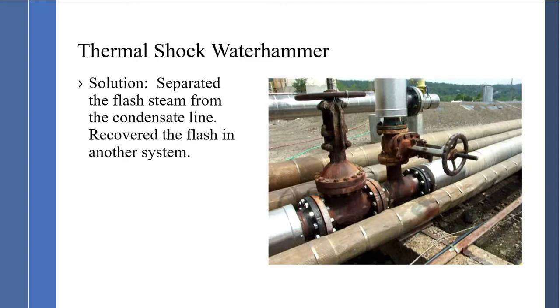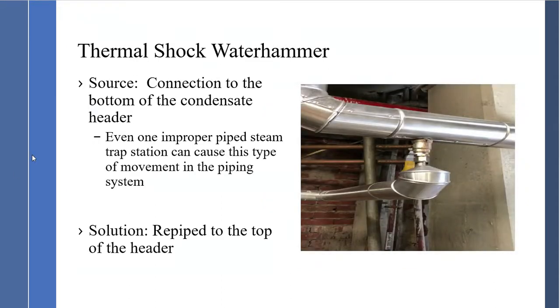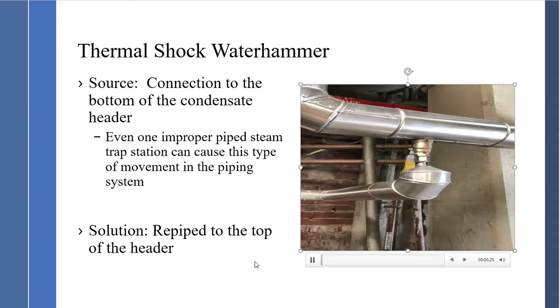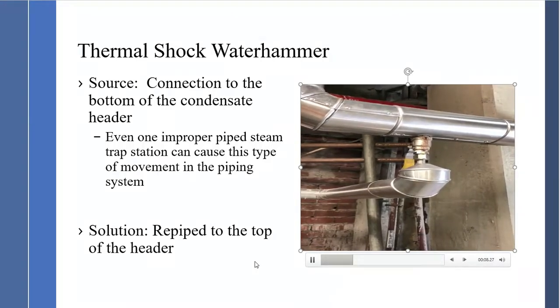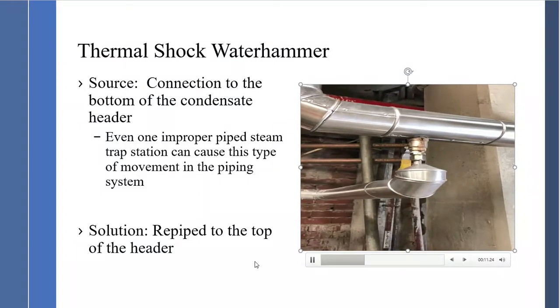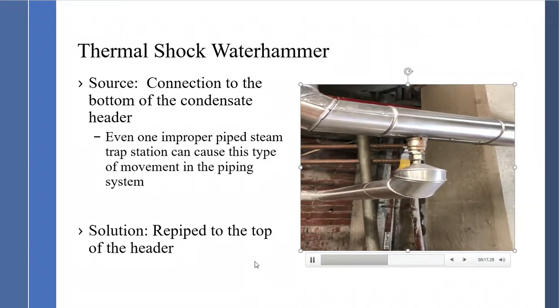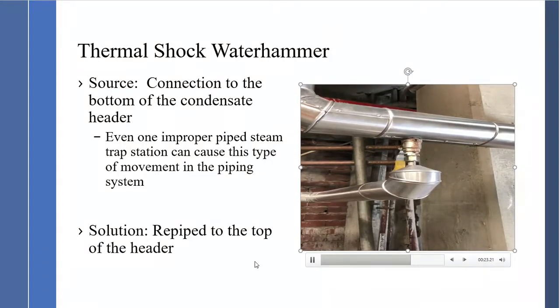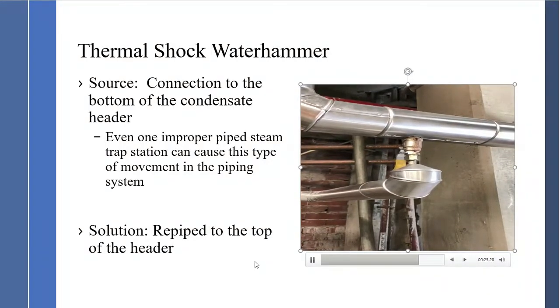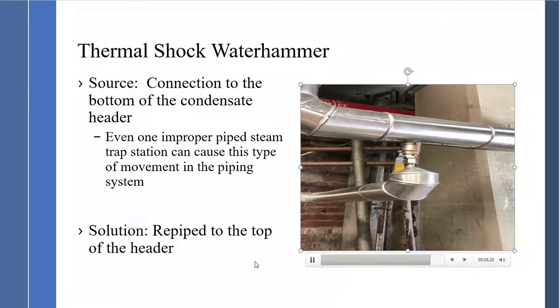Another water hammer example is from a single steam trap. You can see the movement in the pipe caused by just one steam trap and the severity of movement occurring in the piping system. The solution was simply to re-pipe to the top of the header, and the water hammer went away. Even one connection can cause this severity of thermal shock water hammer.